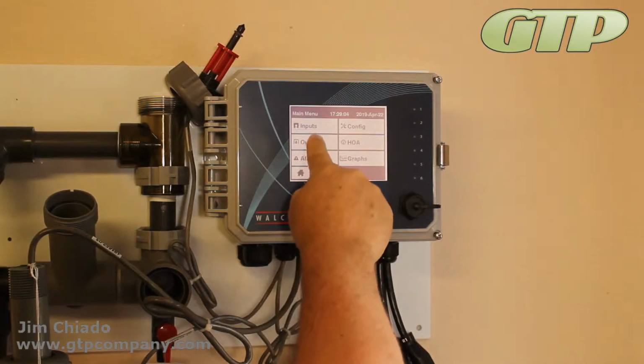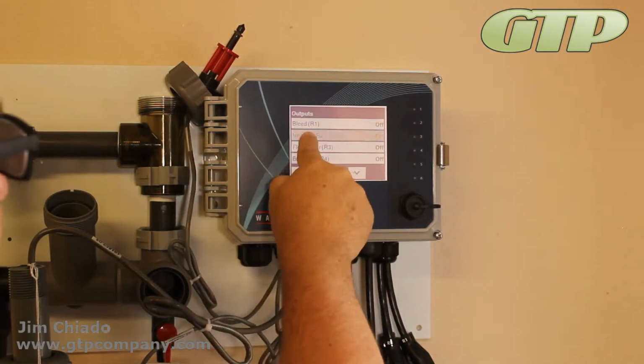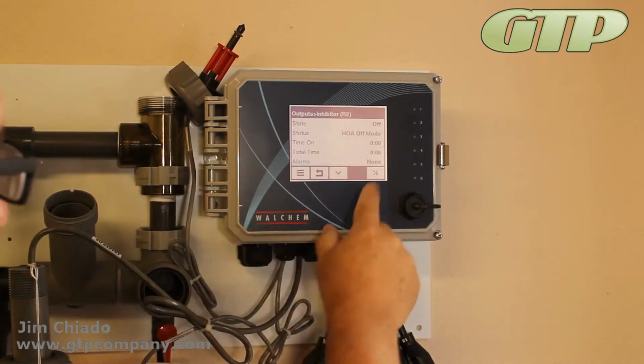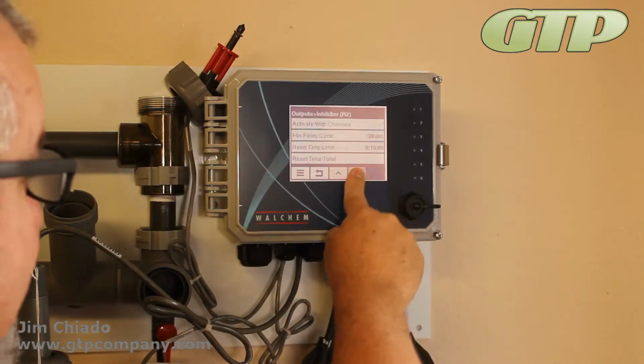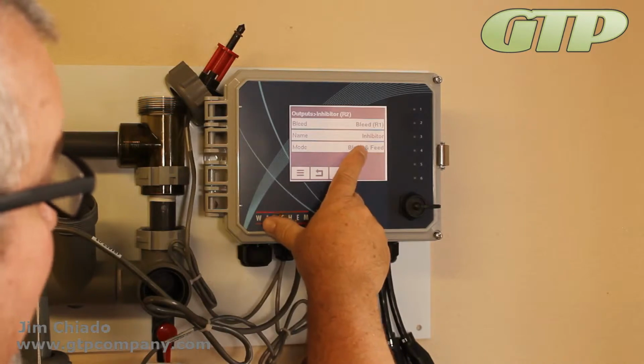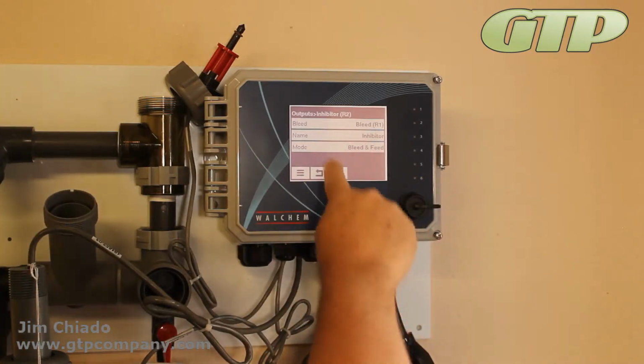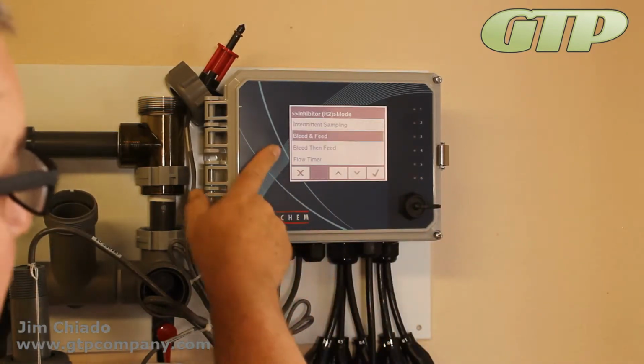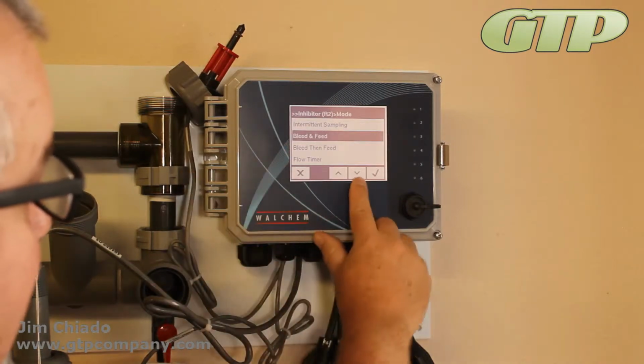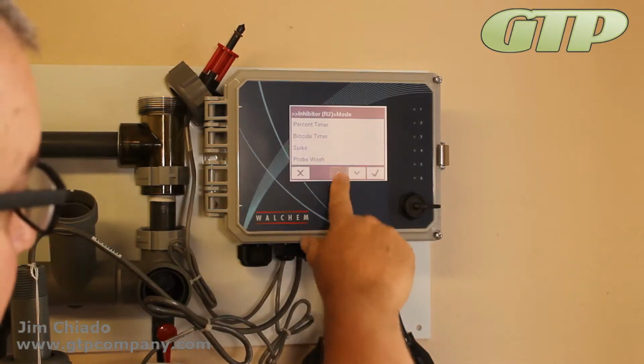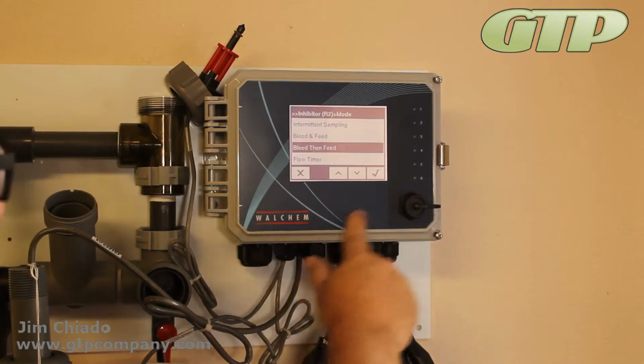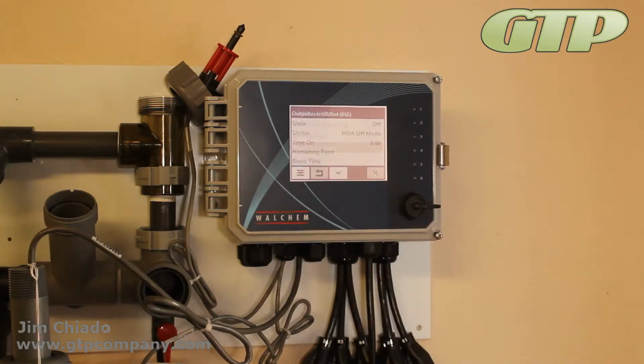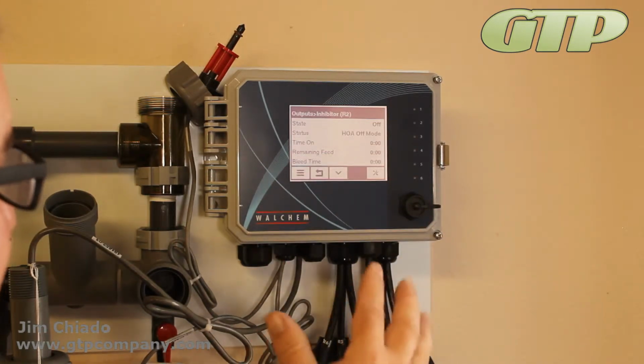I'm going to hit my menu, go into my outputs, R2, which is inhibitor. Right now if I hit the maintenance, I'm going to pan down to the bottom. And you can see it's bleed and feed, which means it does them at the same time. So I'm going to hit the mode, and right below it, bleed then feed. That's not what I want to do. Bleed then feed.